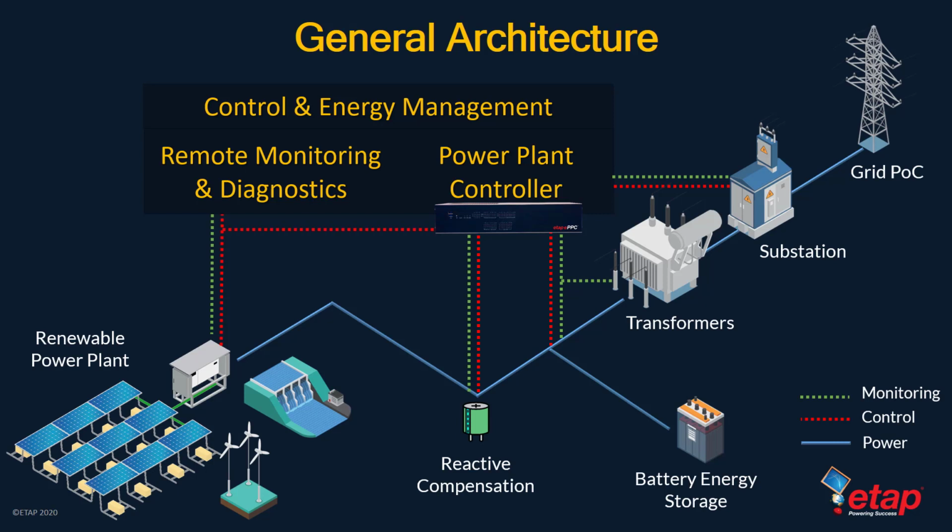Modern day power plant controllers are designed to collect feedback from the grid from the point of connection or point of coupling and adjust the plant output to provide voltage and frequency support. This quality-controlled AC power output is collected and combined from many inverters. Like any other utility-scale system, the output is stepped up and distributed through a substation.